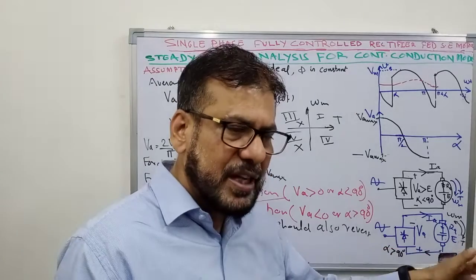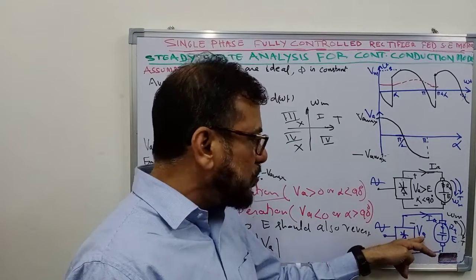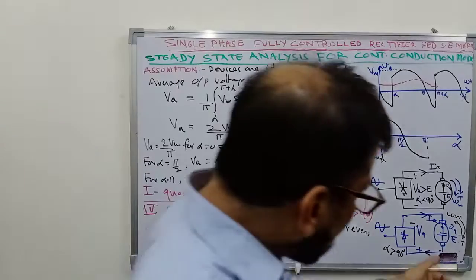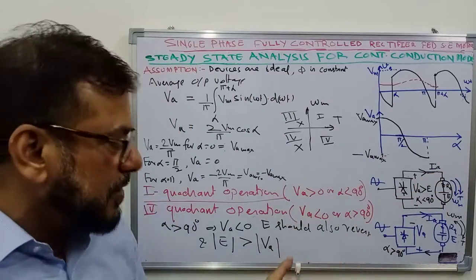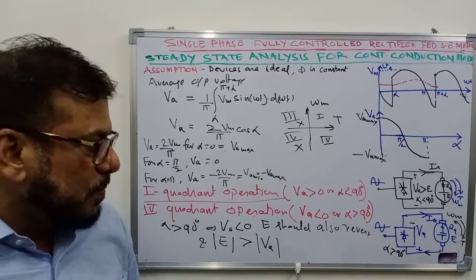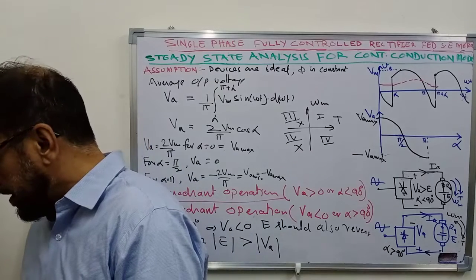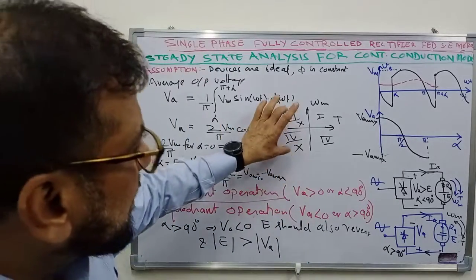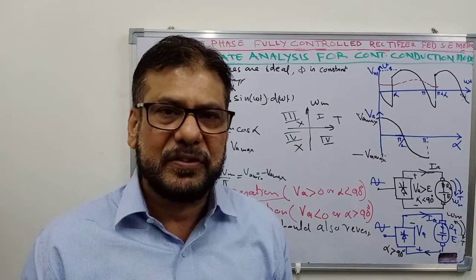You gradually increase alpha beyond 90 degrees and maintain a value of alpha that causes Va to be slightly less than E, so that current continues to flow and braking operation is sustained. Energy is fed back to the source. So these are the two possible modes of operation — first quadrant (forward motoring) and fourth quadrant (regenerative braking) — in the rectifier controlled DC drive. Third and fourth quadrant operations are not possible in this configuration.